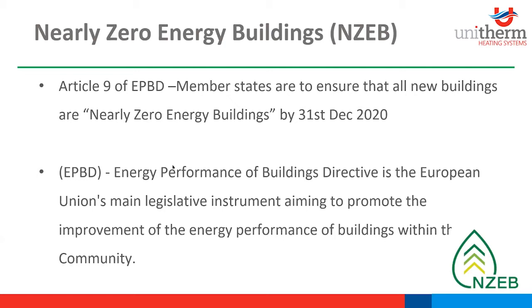So I suppose this is where heat pumps come into play, like your on-site renewable energy production. Heat pumps have become increasingly popular as a renewable source of energy. A low temperature air source heat pump ticks all the boxes when it comes to compliance, ease of installation and consistency of energy production. They have a high COP, so that's coefficient of performance, low running costs, and they're easily maintained, easily serviced. Preventive maintenance is very easy, once a year. Low temperature air to water heat pumps operate most efficiently at 30 to 35 degrees. And this is why we utilize underfloor heating anytime possible, because with underfloor heating we have a larger floor area and a smaller flow temperature.